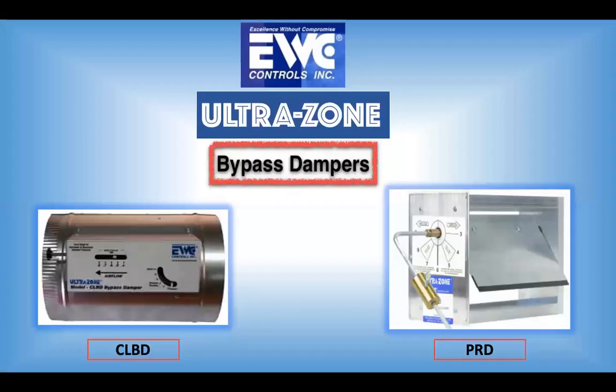Now, for any reason, and I'm thinking of budget, or you're looking at a larger number of homes for new construction, you're looking at getting by without going to the high end of the best bypass damper made, we do have mechanical bypass dampers, both round and rectangular. Now the electronic, the SBD, is available in sizes 8 to 20 and 6 different pre-made sizes in rectangular. The round damper, mechanical damper, CLBD, is available in 8 to 16 and the rectangular damper in 6 different ranges.